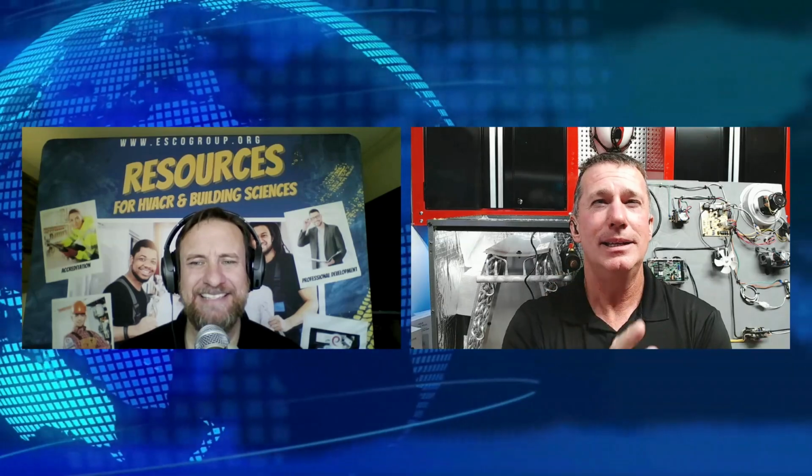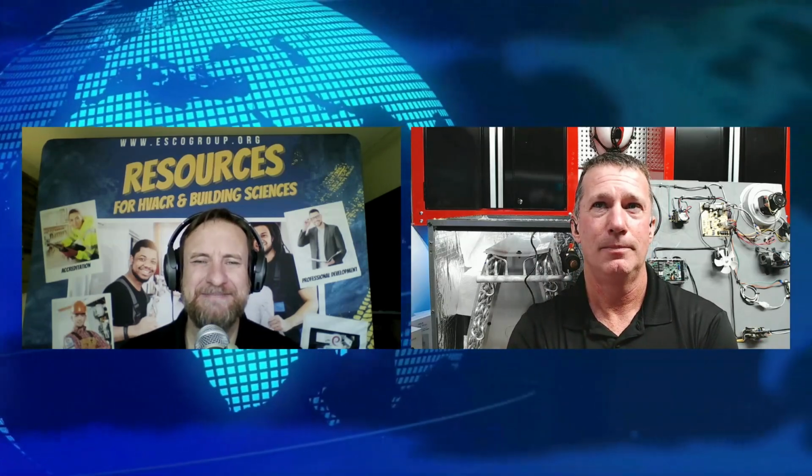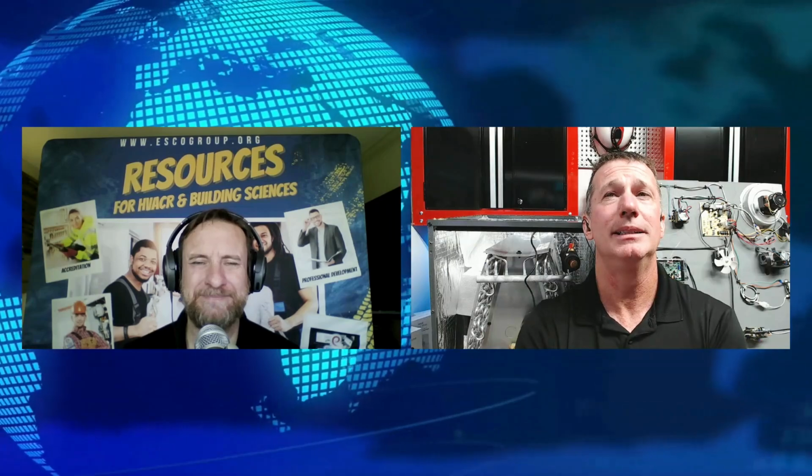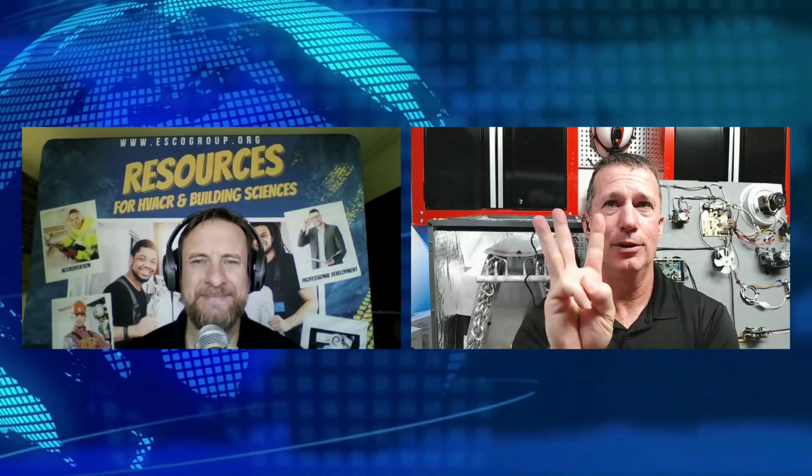But no, think about this for a second. What is mitigation? Mitigation is an action or sequence of actions that is tied to a change of state. And I stump people in this class because I want you to think about this. If we take a gas furnace, Todd, you're going to appreciate this very much. You love sequence of operation of things. I have a gas furnace and I fail to ignite. I've got a call for heat. I try to ignite. I do not ignite. And I do that 3 times in a row. What happens after that third attempt?